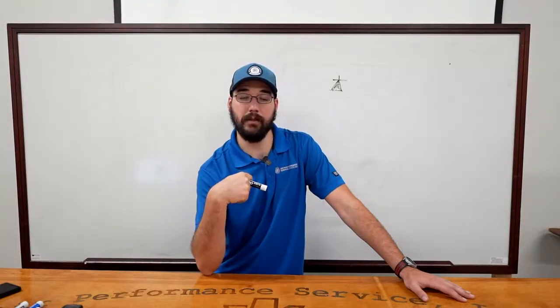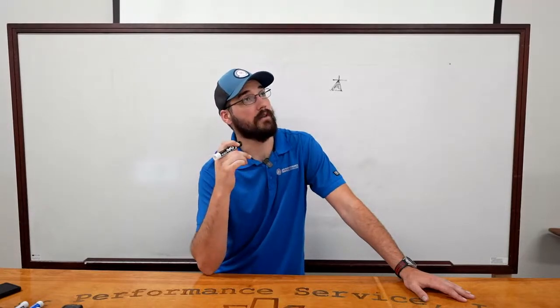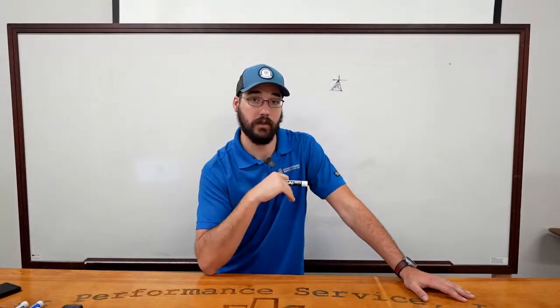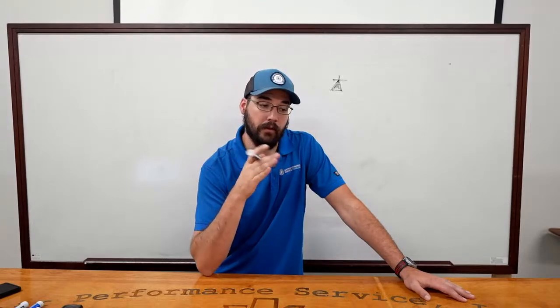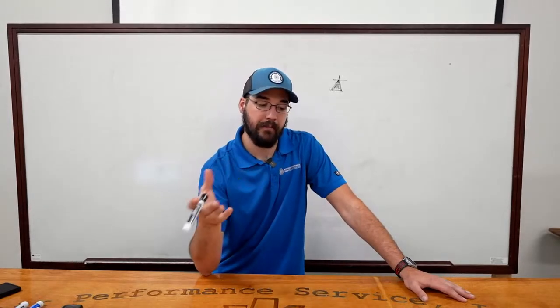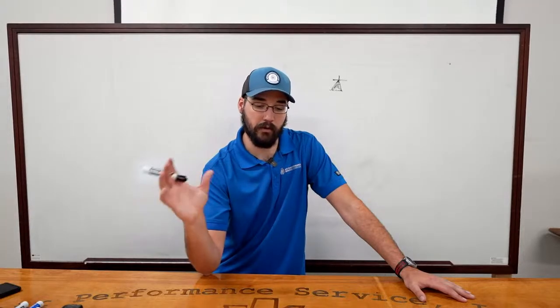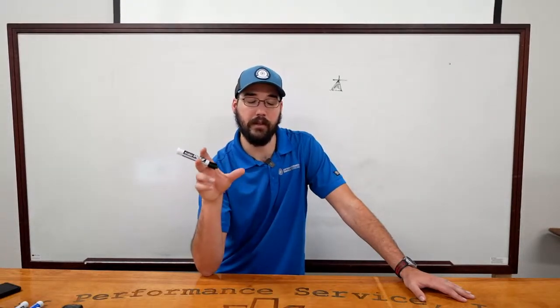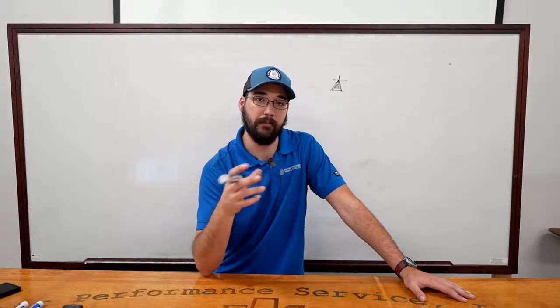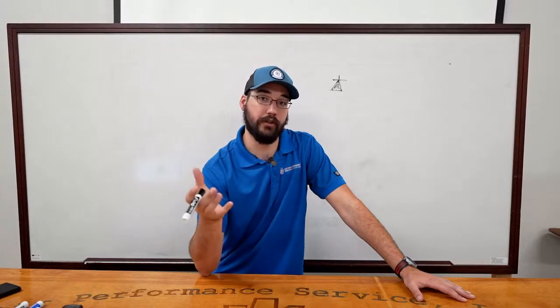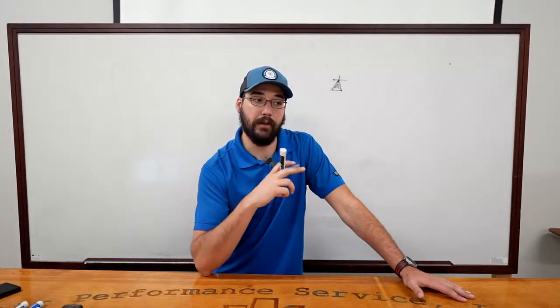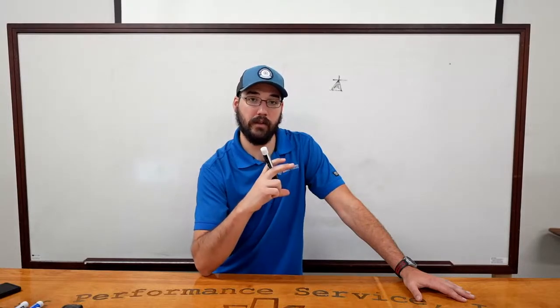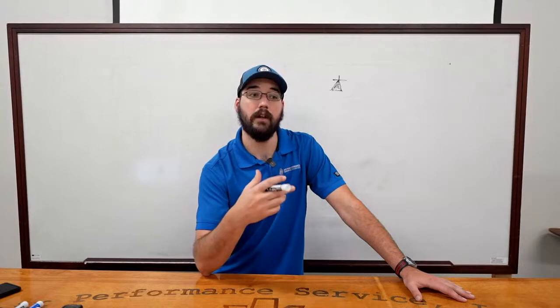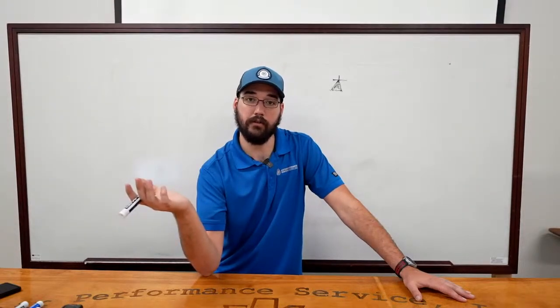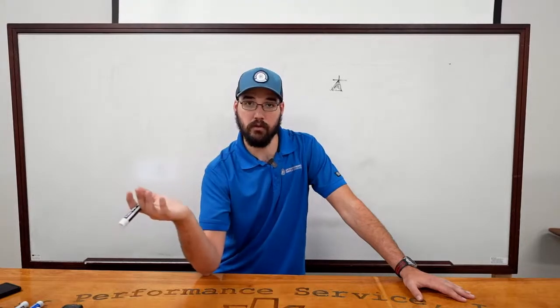I had that scenario happen to me where we had a blower motor go bad. This was several years ago, and it was on a ducted indoor unit. Blower motor went bad. Tech support verified, they confirmed the diagnosis, got the new motor in, and it started generating other alarms. Well, then we ended up condemning the control board at that stage. So we went ahead, replaced the control board. Well, then the blower motor started registering bad again. We started having issues on the blower motor side.